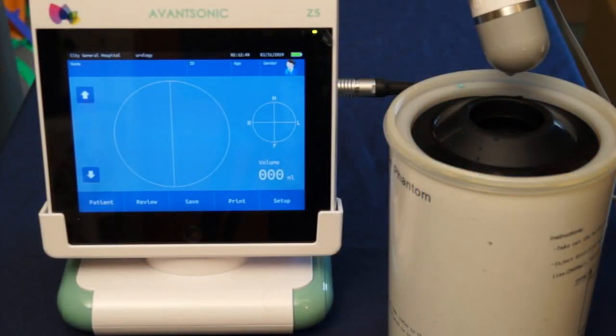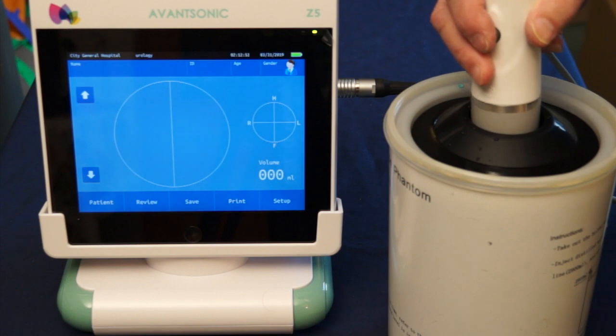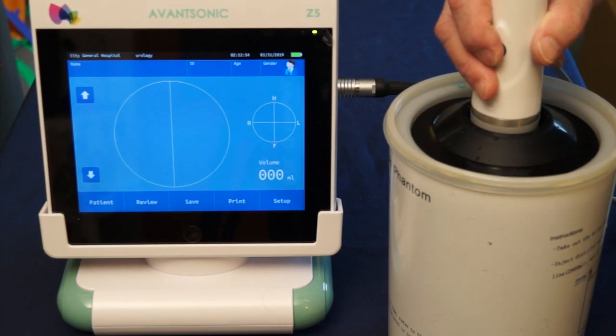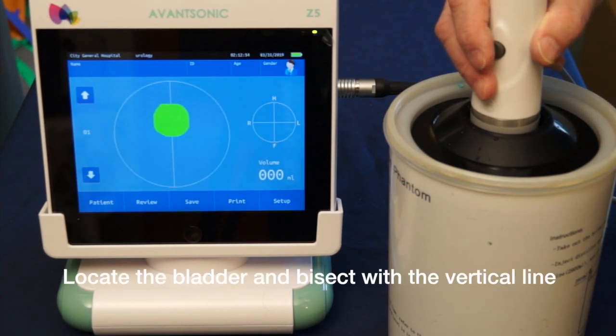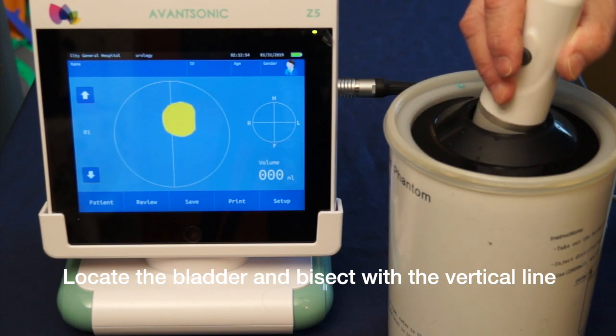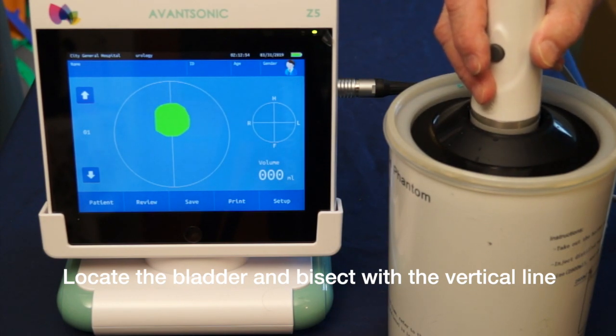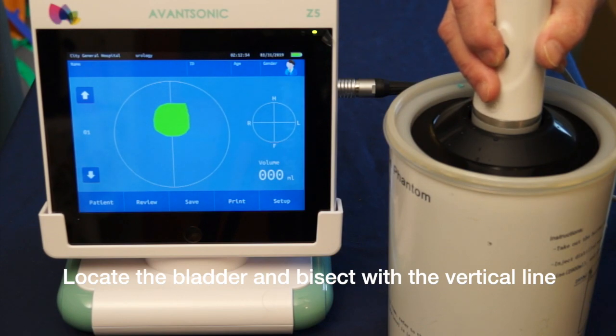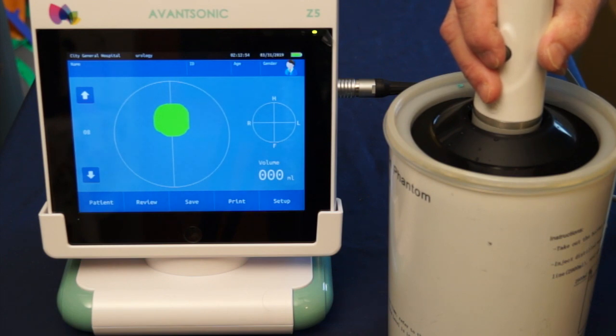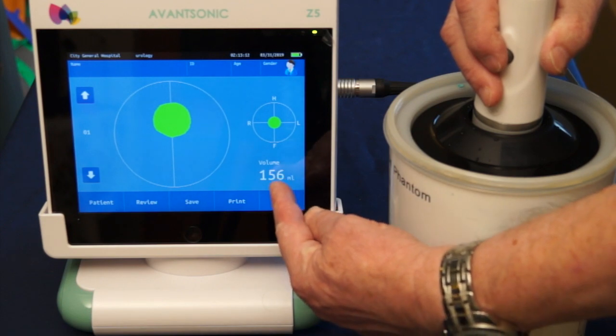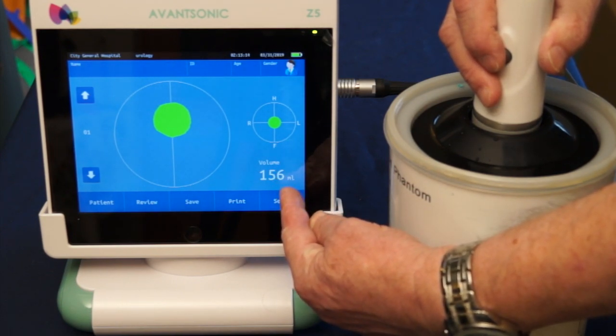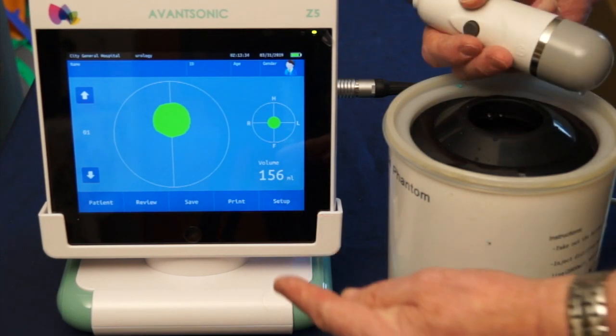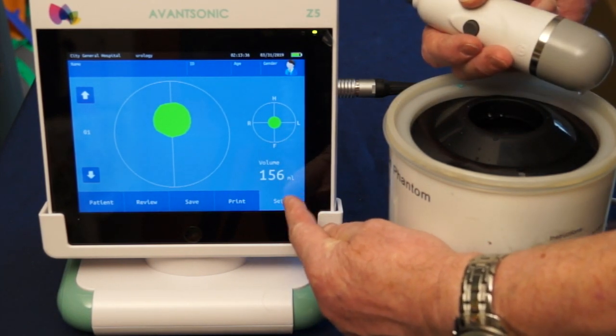For the purposes of demonstration, I have a phantom bladder. I'm going to insert the probe and press the button to establish pre-scan, and you'll see as I move the probe around the image changes from green to yellow and back to green. Green is good, and I'm going to bisect the green image with the vertical line and then press the button again. It's now counted up to 12 and it reads out the volume at the base right hand corner of the machine. Basically both images showing green is good.